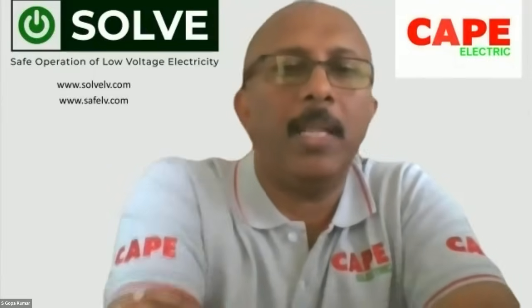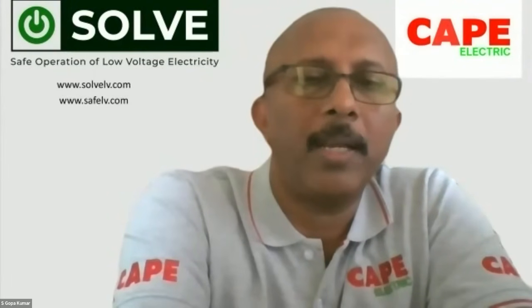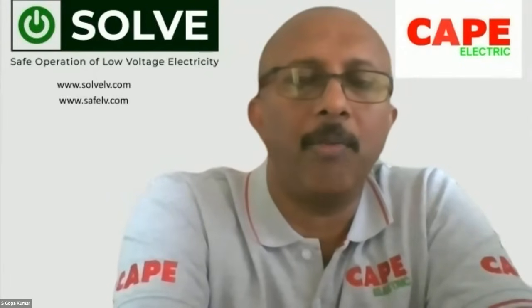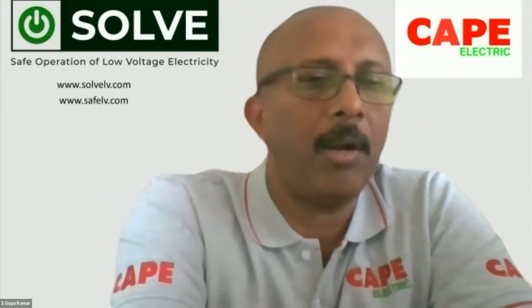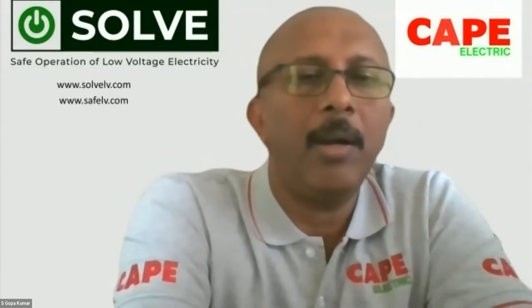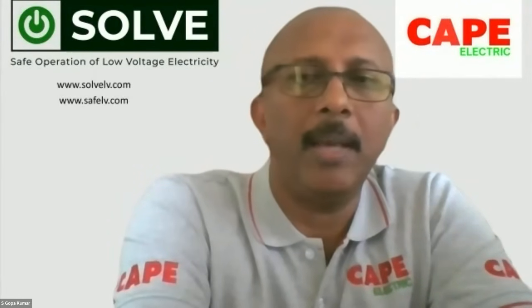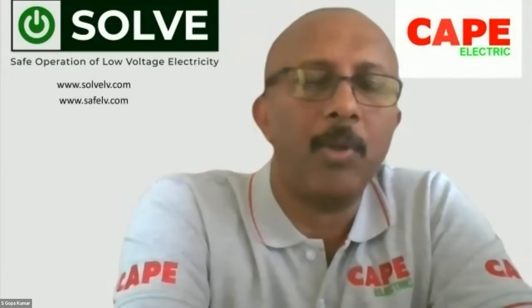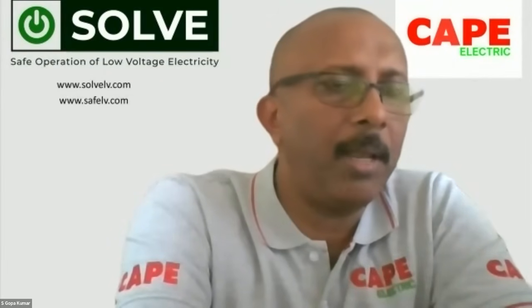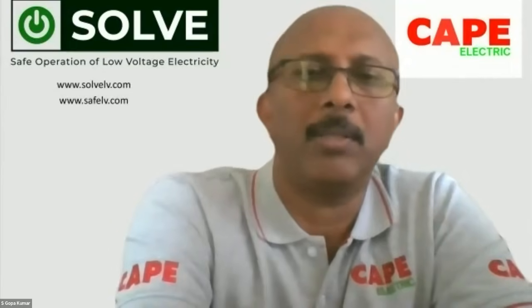I am unable to get the question. I think you were asking, you have mechanical contactors in your automatic power factor correction or in some of the panels, and these contactors are burning. Of course, in capacitor switching, contactor burning is quite common because the inrush current of the capacitor is quite high. As a result, the contactor joints either get welded or damaged. I really don't know how this problem is solved. I have seen some companies having special capacitor duty contactors. You should use those special contactors, not the normal one which is used for motor duty. Or another option is to use a thyristorized controller. Yes, thyristorized, the semiconductor-based switching device, which will switch on the capacitor during the zero crossover.